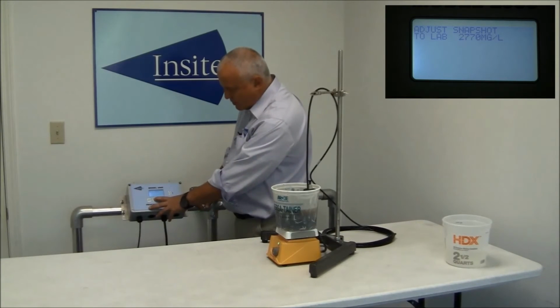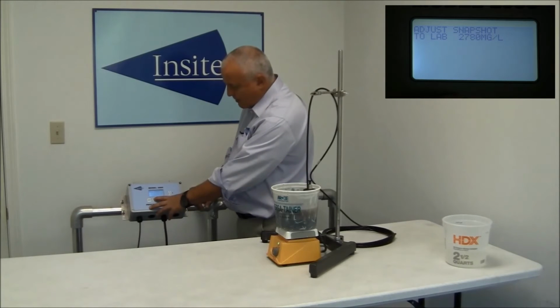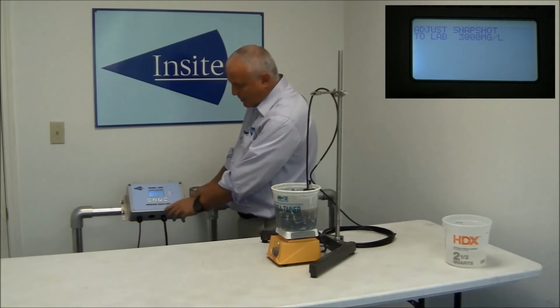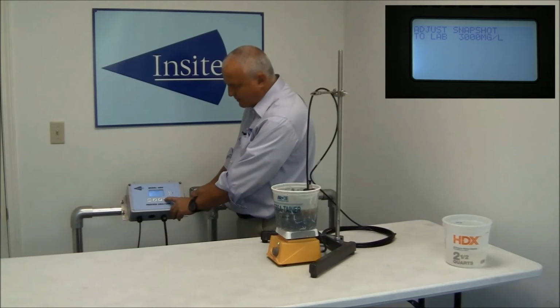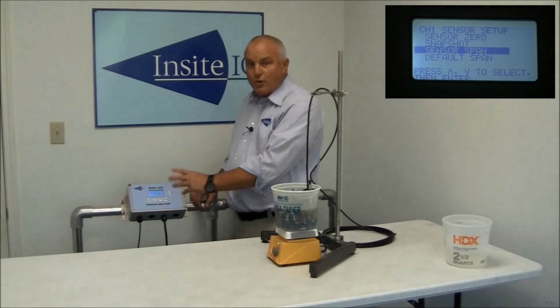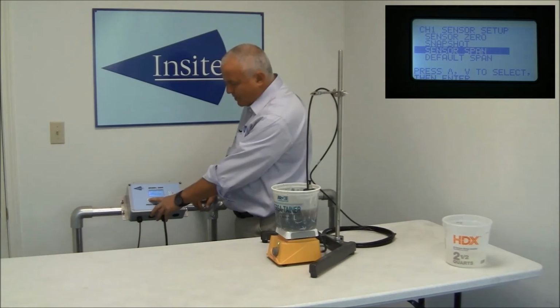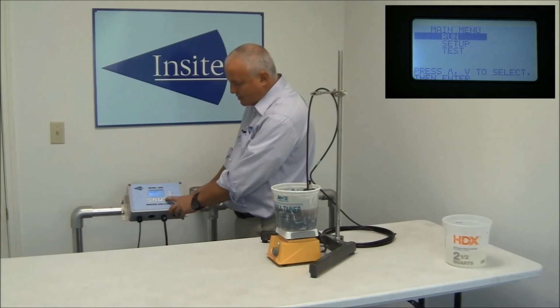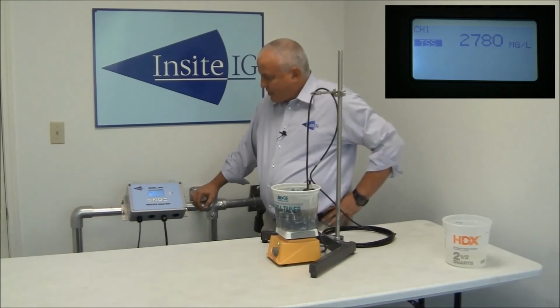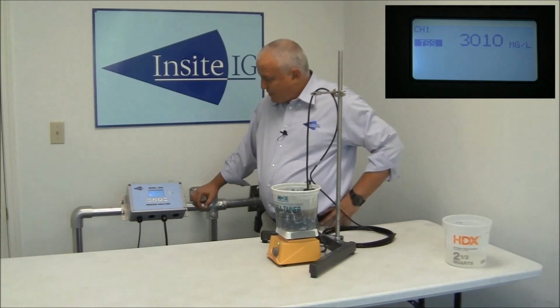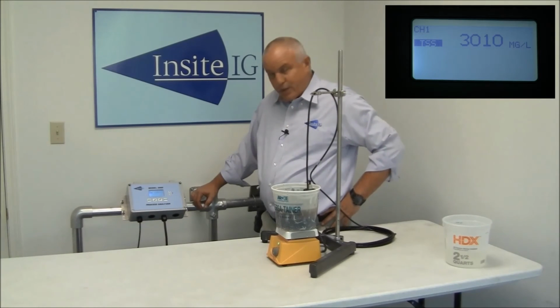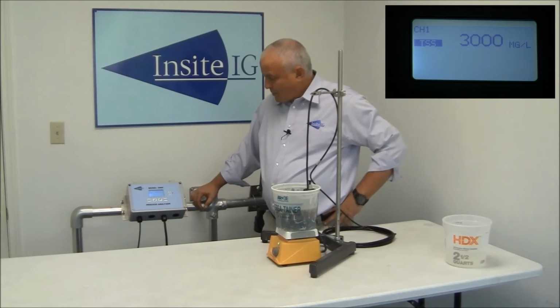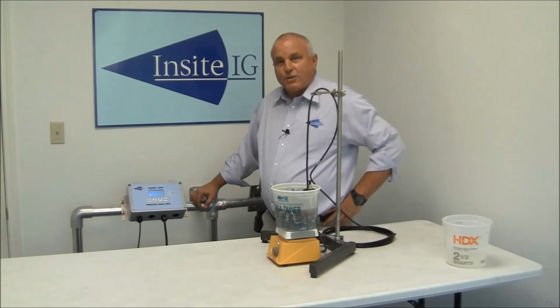Let's say the lab came back and said 3000. You just use the up arrow key, put it up to 3000, press enter. You've just stored the new curve based on your lab sample. Menu to back out, menu to back out. Once you get to run, select run. It's going to take a second or two for the buffer to fill. Once the buffer fills, it should come up with pretty close to the 3000. You can see it. And that's all there is to the calibration.